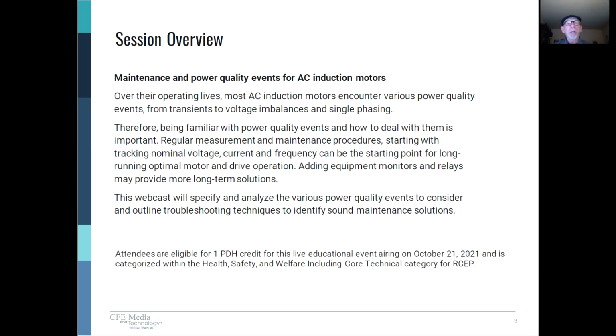Over their operating lives, most AC induction motors encounter various power quality events, from transients to voltage imbalances and single phasing. Therefore, being familiar with power quality events and how to deal with them is important. Regular measurement and maintenance procedures, starting with tracking nominal voltage, current, and frequency, can be the starting point for long-running optimal motor and drive operation. Adding equipment monitors and relays may provide more long-term solutions.